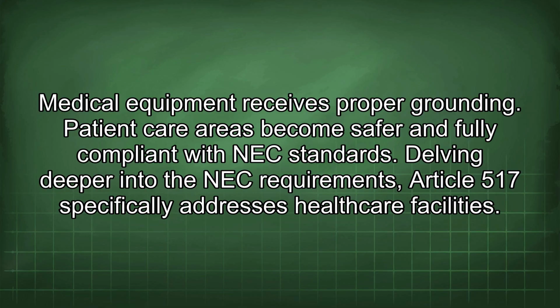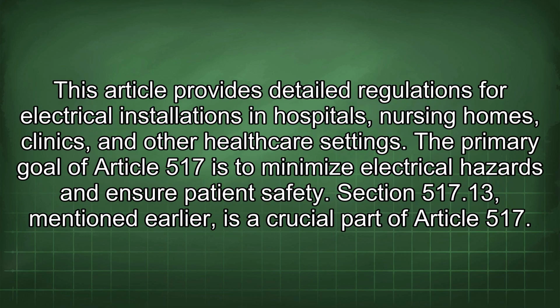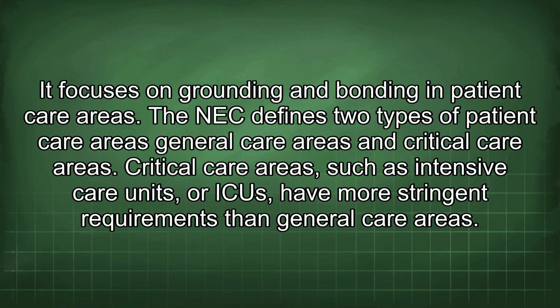Delving deeper into the NEC requirements, Article 517 specifically addresses healthcare facilities. This article provides detailed regulations for electrical installations in hospitals, nursing homes, clinics, and other healthcare settings. The primary goal of Article 517 is to minimize electrical hazards and ensure patient safety. Section 517.13, mentioned earlier, is a crucial part of Article 517. It focuses on grounding and bonding in patient care areas. The NEC defines two types of patient care areas: general care areas and critical care areas. Critical care areas, such as intensive care units, or ICUs, have more stringent requirements than general care areas.